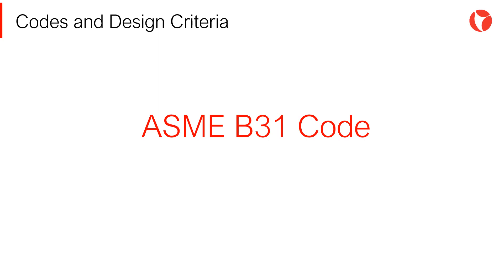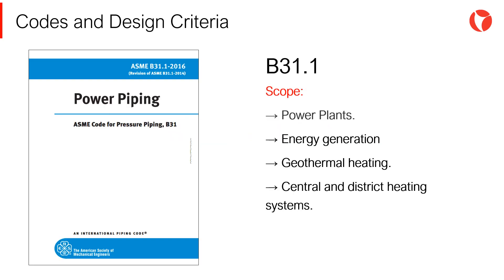In piping systems, the most commonly used design codes are those of the ASME B31. The piping design code ASME B31.1 is applicable to power plants, energy generation plants, geothermal heating, and central and district heating systems.